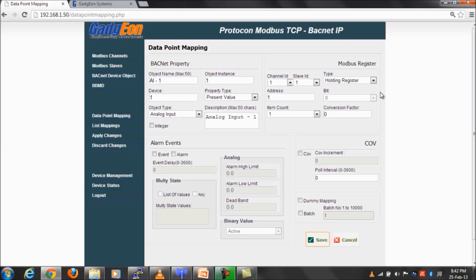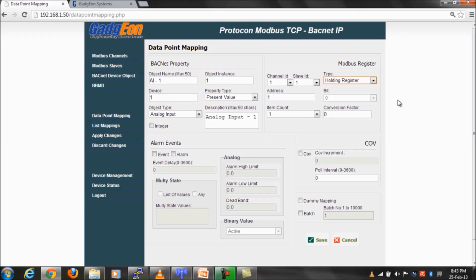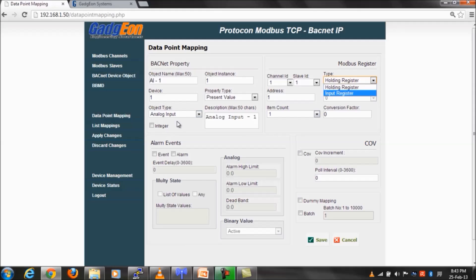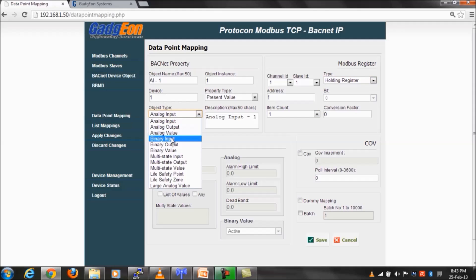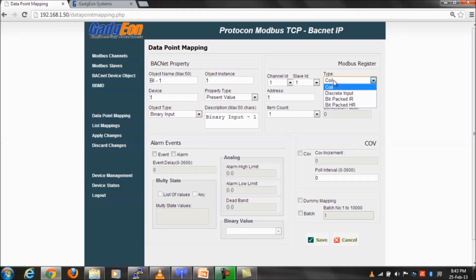This mapping is used by the device software to convert the Bacnet queries to Modbus requests. BACnet object types can be mapped to four Modbus register types: input register, holding register, discrete, and coil.